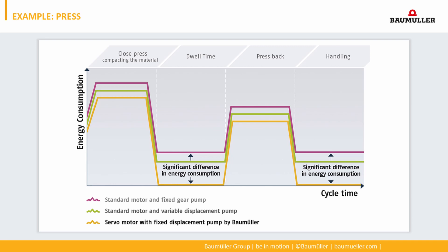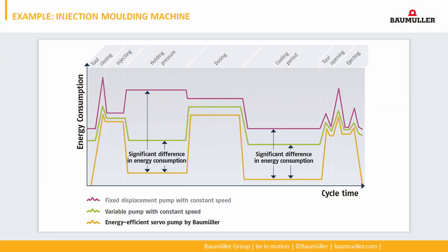During pressing and returning, the energy consumption of a servo-hydraulic system is also a little bit better. The second example shows a cycle from an injection molding machine. Here we see two segments where much energy can be saved: holding pressure and cooling period. During the cooling period, no power is required and the motor in the servo-hydraulic system is stopped. During the holding period, the pressure must be controlled at a constant high level, but no or only very small flow is required. The system with standard induction motor and internal gear pump is very inefficient because of the high flow rate generated at high pressure. The variable displacement pump is better because the flow rate is adapted, but the efficiency is still poor. The most efficient system is the servo-hydraulic system, because the speed is reduced to the level necessary for holding the pressure.